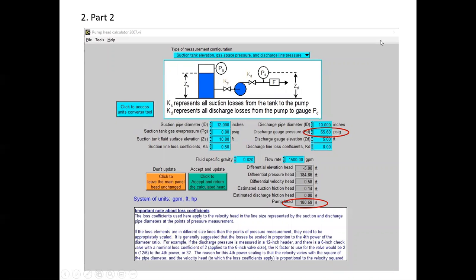Okay, so here is the pump head calculation, and now when we put in this reduced specific gravity, then the pump discharge pressure changes in order to give the same head. If I leave the same discharge pressure, this head goes to like 221 or something. And we know from pump theory that that's not going to happen, that this is going to stay the same. So what you have to do is monkey with this, reduce this pressure until you get 180.59 again. So it's about 65.6 PSIG.